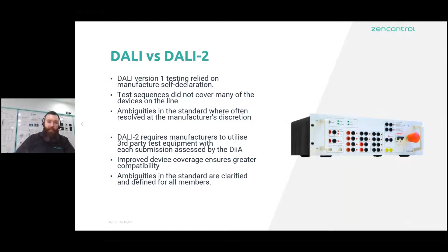Some of the other advantages of using a DALI 2-based system is that we're typically moving the control and configuration back to a device that's network connected or sitting at a central point—the application controller we talked about before—which looks after all the configuration, all the commands, how the sensors operate, and the sequences.